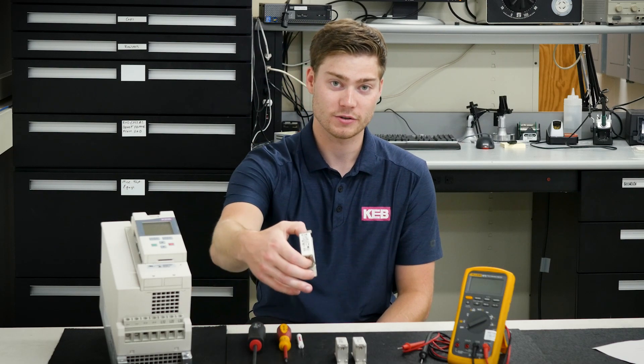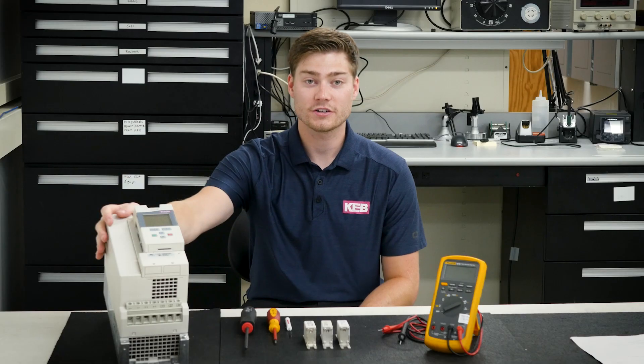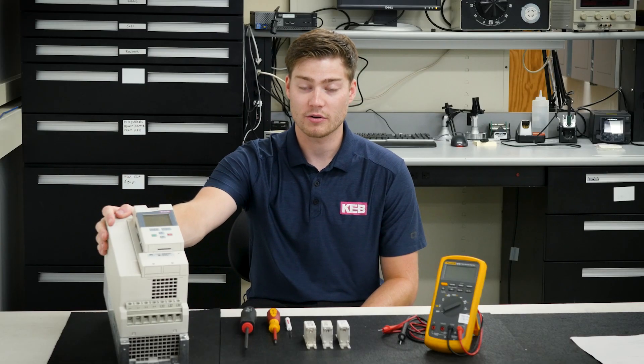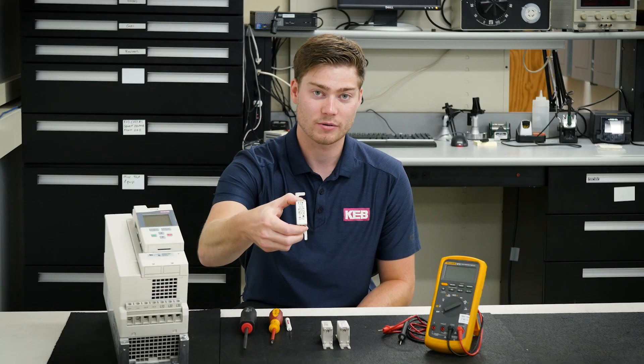Today we'll be talking about how to replace the fuses on an R6 Regen Unit. My name is Eric Danner and I'm an Elevator Applications Engineer here at KEB America. The R6 Regen Unit, typically found in Elevator and Hoist Applications, takes energy that is typically wasted and converts it into usable electricity that can be fed back onto the grid. A power surge or short inside the F5 or R6 may cause a fuse inside the R6 Regen Unit to blow.